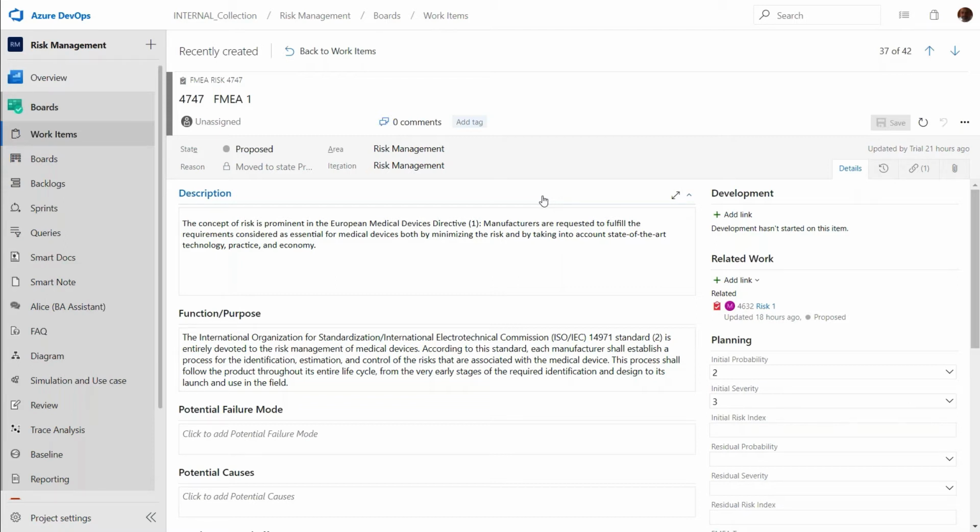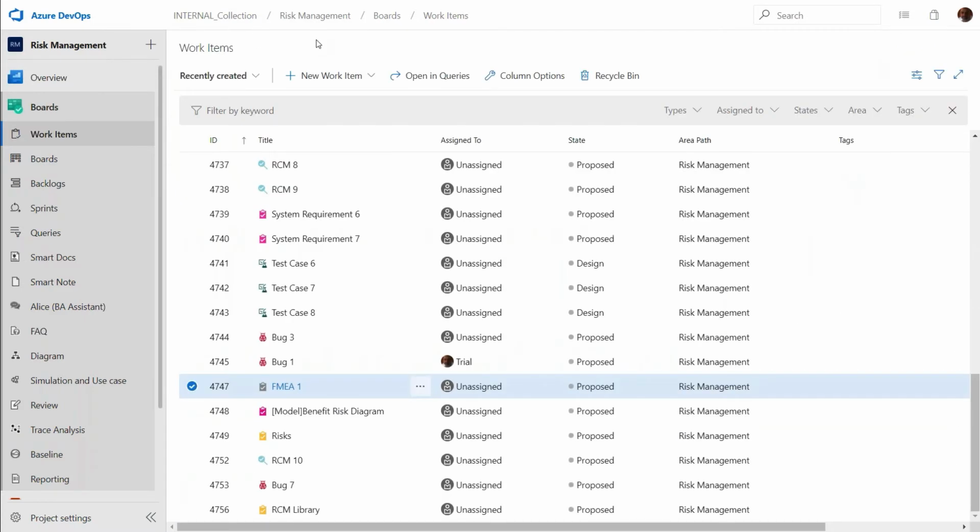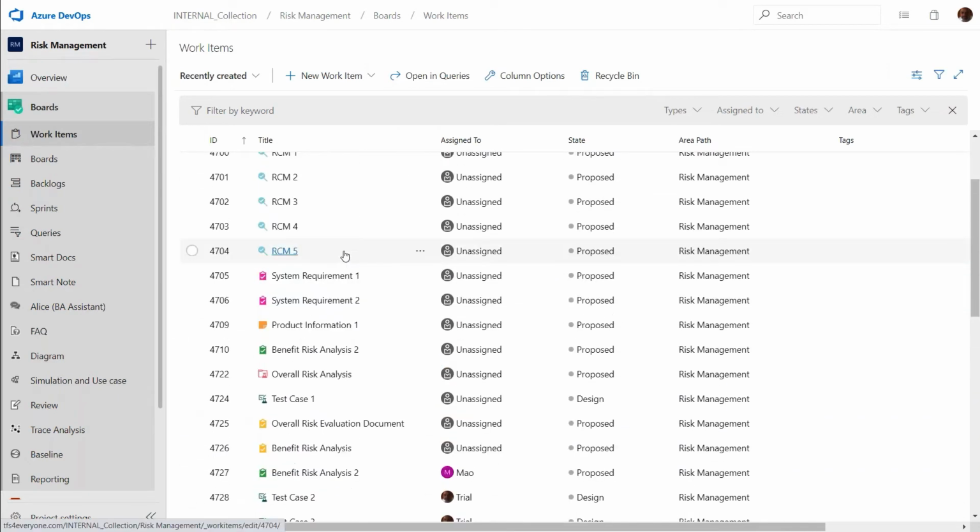And most of our medical device clients use both approaches for a single device. However, if you are using FMEA only for your risk management efforts, you are not meeting the intent of ISO 14971. So in this webinar, we will mainly focus on the hazard risk analysis, which is a top-down approach.